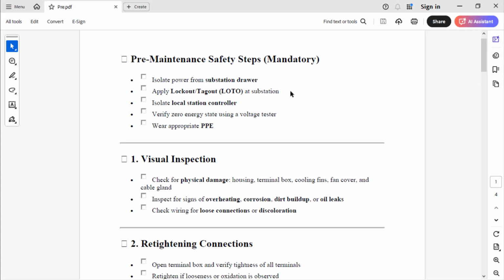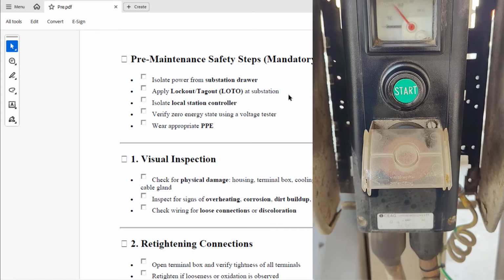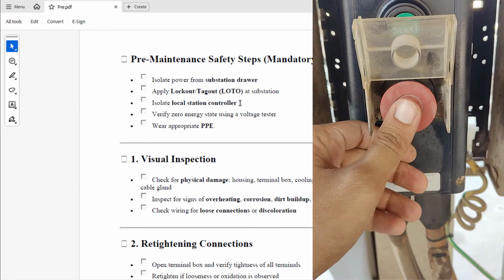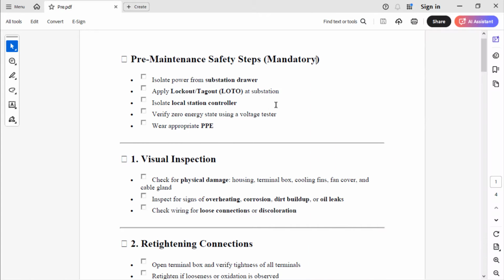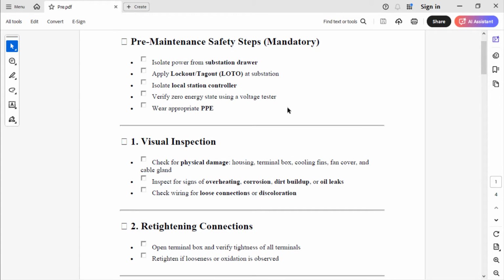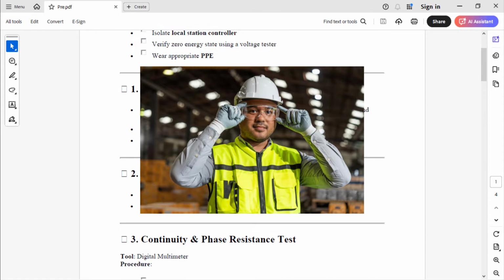Also, we apply lockout and tagout (LOTO) at the substation. We put locks and give every person who is responsible for working on this motor a lock. We also isolate the local station controller to be more assured that it will never work. So we isolate the start-stop local station controller. Also, we verify zero energy state using a voltage tester and wear appropriate personal protective equipment.